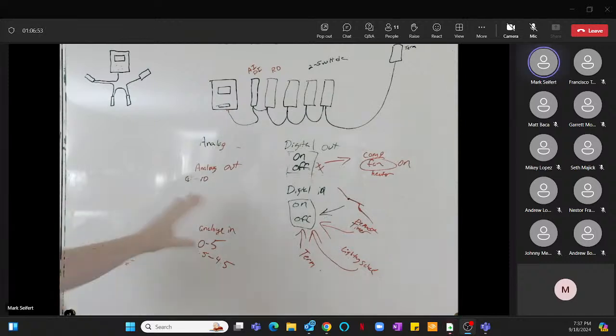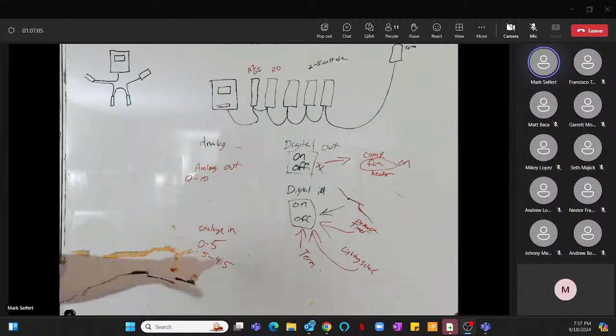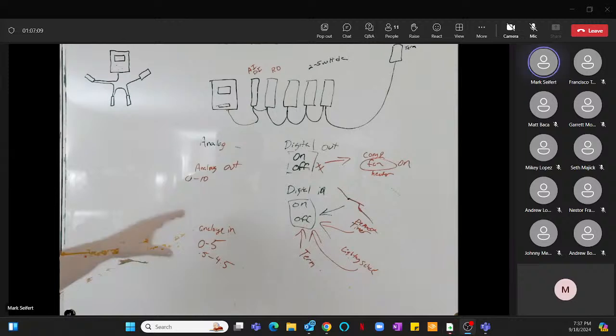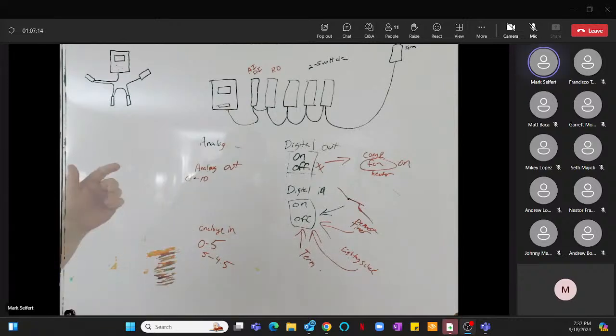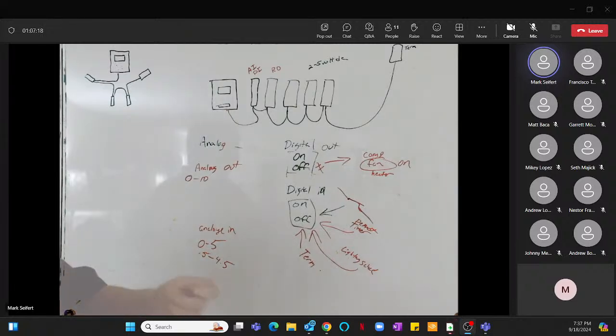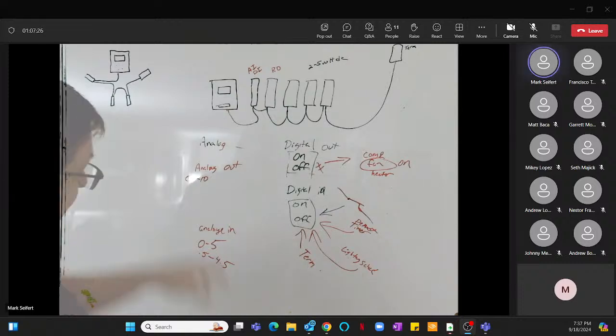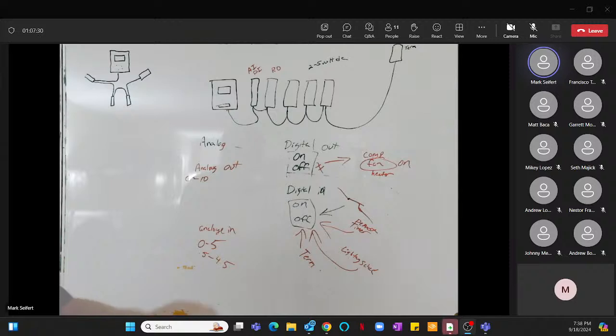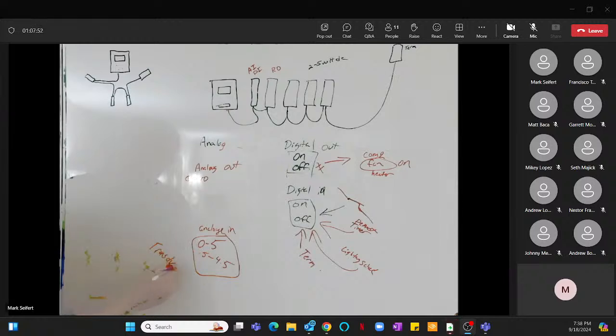Okay, let's get into the wiring of transducers and sensors. Analog inputs aren't just a transducer, but a voltage input. A sensor is a resistance input. The boards are always putting out voltage, just like your voltmeter. When you ohm something out like a compressor, you see the resistance in it, these are doing the same thing. Your voltmeter, if tested with another meter on ohms, is actually putting out voltage, and it knows the resistance by how much voltage comes back. So let's see what we can come up with: analog ins, transducers, sensors.